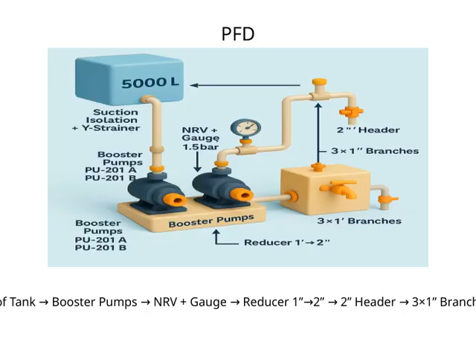Starting from the roof tank, the fluid flows downward to the booster pumps, which are essential for maintaining the required pressure and flow rate. From there, it moves through the NRV, or non-return valve, to prevent backflow, and a gauge to monitor the pressure levels. Next, it passes through a reducer, going from 1 inch to 2 inches in diameter, which helps manage flow rates efficiently. After that, the flow continues through a 2-inch header, serving as a main distribution point. Finally, this header branches out into 3 1-inch lines, which distribute the fluid to different parts of the system.